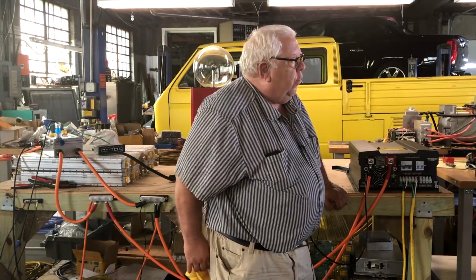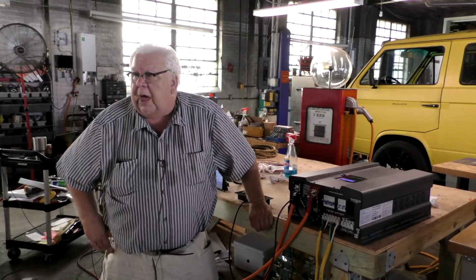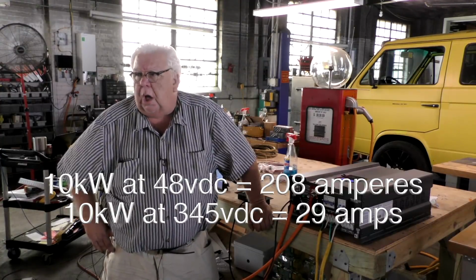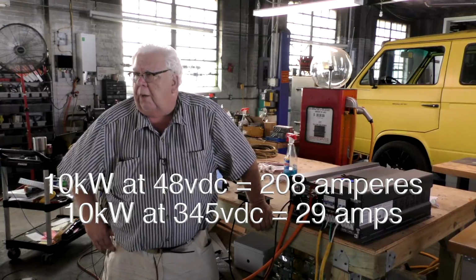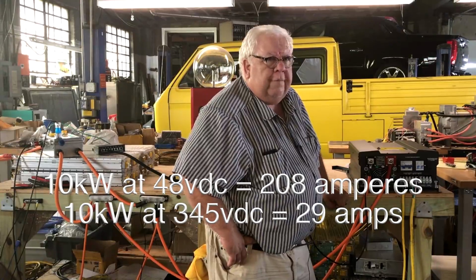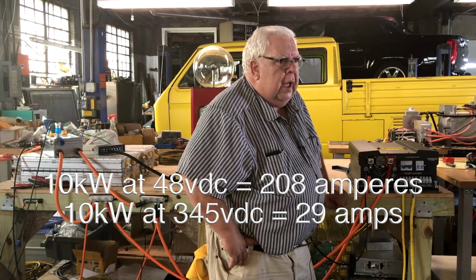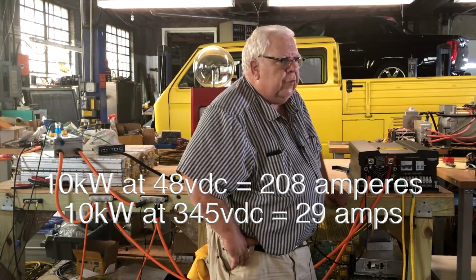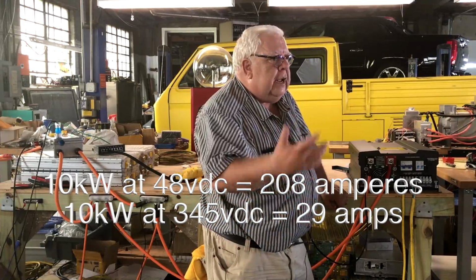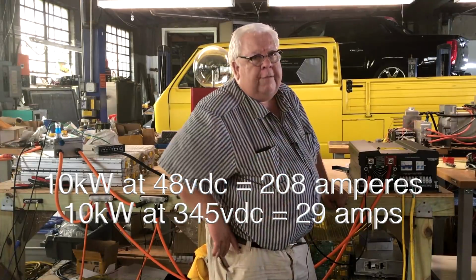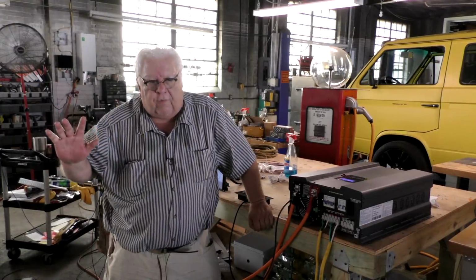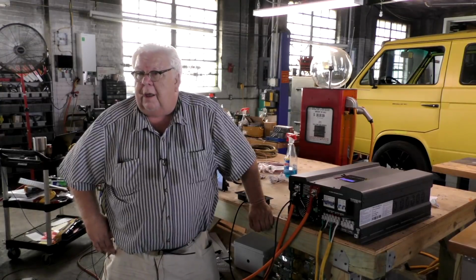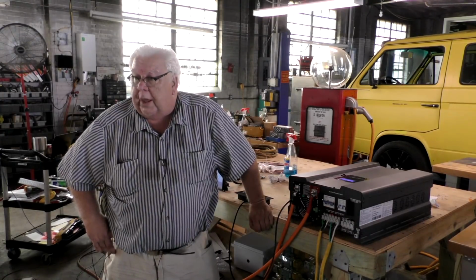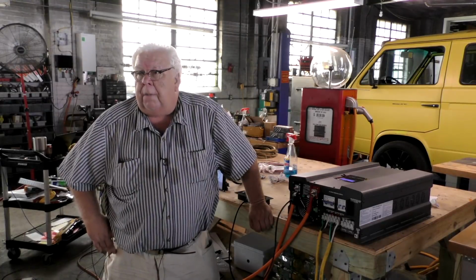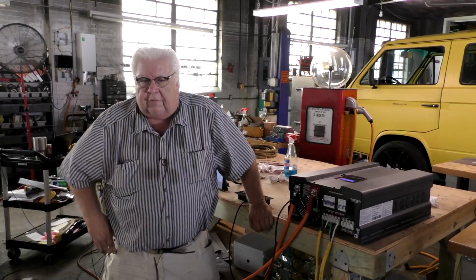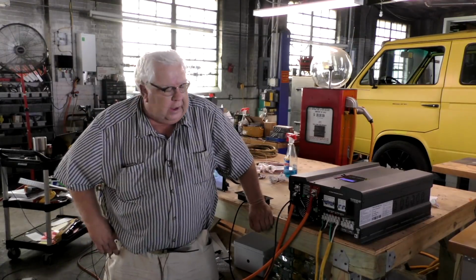There's a few problems with that whole theory. One has to do with current. We've got to do a couple hundred amps of current to do 7 or 8 kilowatts of electric power generation at 48 volts. That same amount of power at 345 volts is 23 or 24 amps. And so all our wiring and our heat issues and so forth go way down, and life gets much simpler. However, I'm being overruled by our viewership and demand for product at EVTV right now. Everybody wants our 48-volt system controller, and they want to deal with individual Tesla battery modules. So for that now, that's what we've got going on.